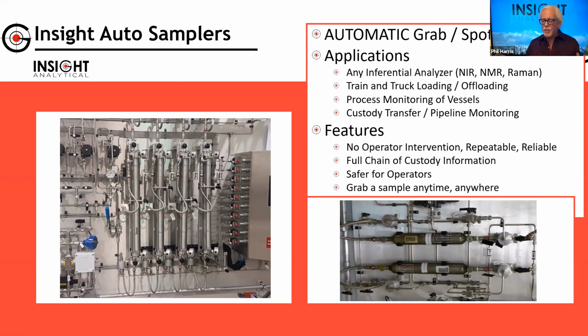When we talk to people at the labs, they say the two biggest problems are either the person who pulled the sample didn't know how to do it properly. If it's a volatile liquid like propane or condensate and they let bubbles escape, they get a bad sample. Or if it's butane blended crude, they get a bad sample. If they don't pull at the right speed, or don't allow systems to purge long enough, all of these things lead to a bad sample. So that's one of the big issues labs have: people don't pull samples properly.